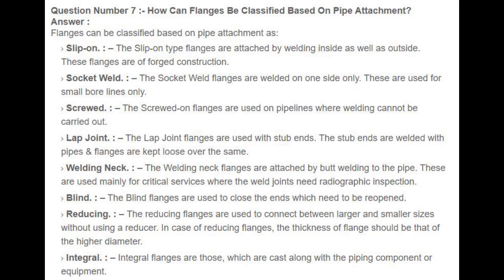Question number 7: How can flanges be classified based on pipe attachment? Answer: Flanges can be classified based on pipe attachment as: Slip on — attached by welding inside as well as outside, these flanges are of forged construction. Socket weld — welded on one side only, used for small bore lines only. Screwed — used on pipe lines where welding cannot be carried out. Lap joint — used with stub ends; the stub ends are welded with pipes and flanges are kept loose over the same.